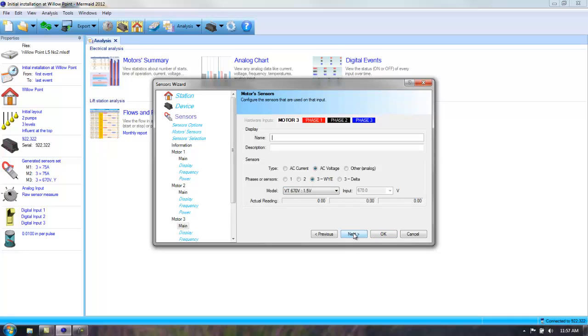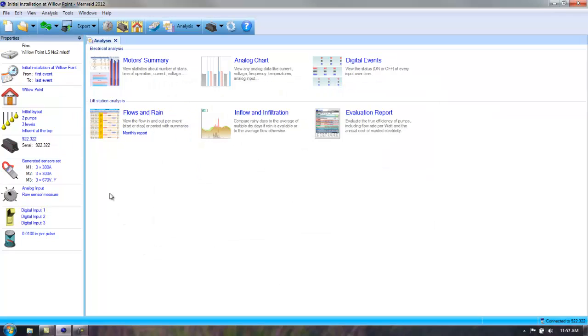Well, I can also go next and it will go to motor 3. Well, motor 3, we knew we were monitoring the AC voltage through a Y connection. I'm going to go ahead and say the display name is going to be voltage. And then I want to hit OK. If you notice, down the generated sensor set, it's now 300 amp clamps. And that is the end of setting up a generic duplex station file.